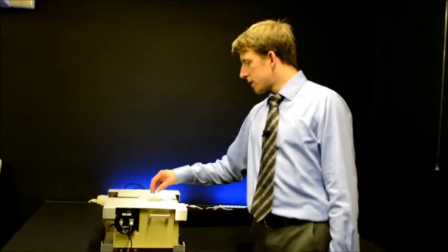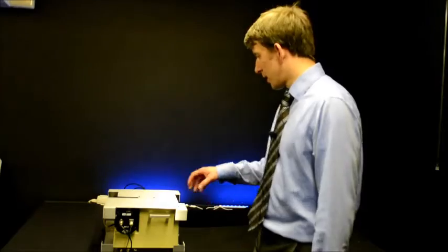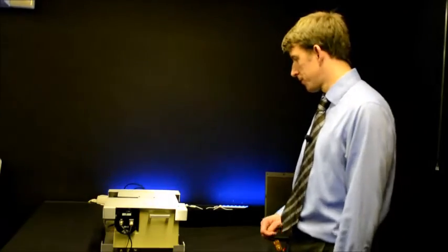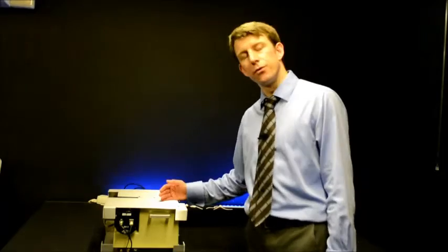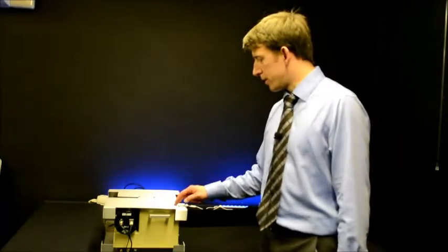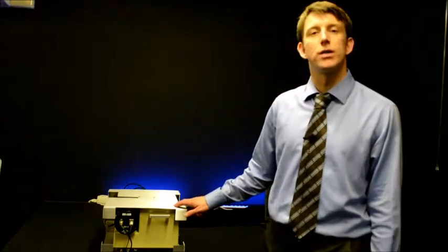The dmc150 monochromator is composed of two component halves, two 150mm monochromators in additive dispersion mode to yield a 300mm focal length double monochromator. Light entering the entrance port is relayed through 45 degrees by a plane mirror and is impinged upon a spherical mirror of 150mm focal length.